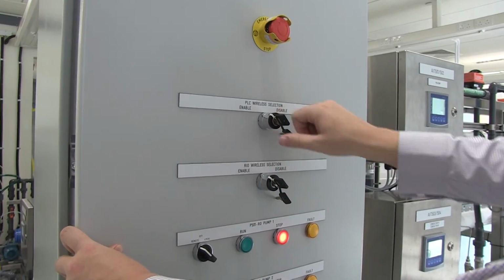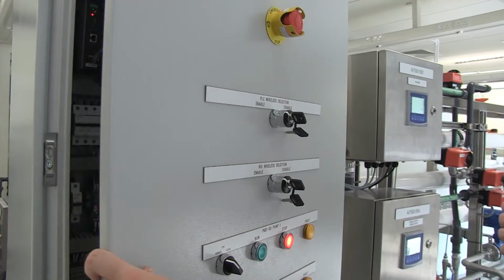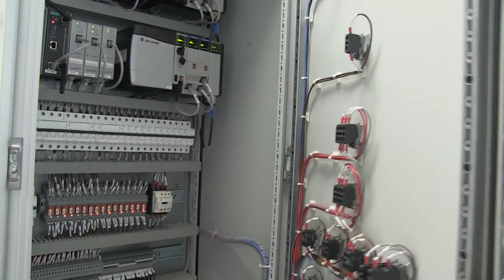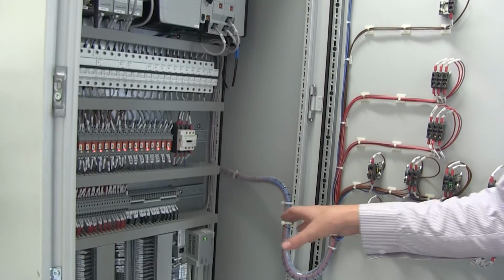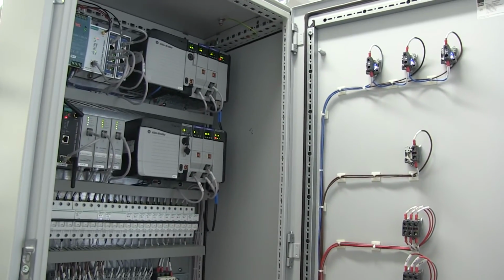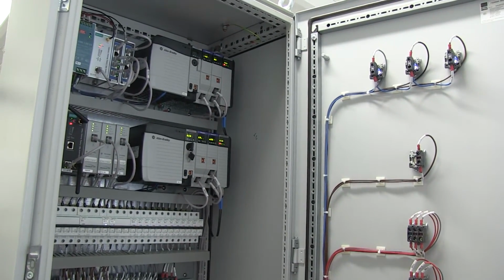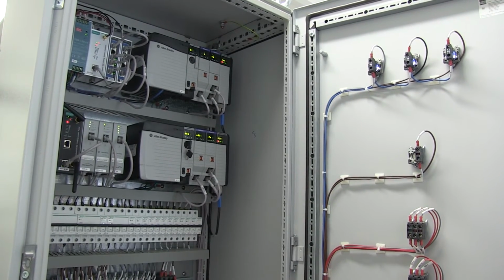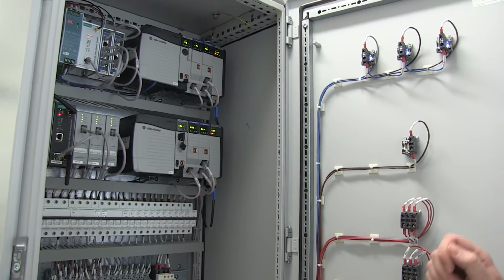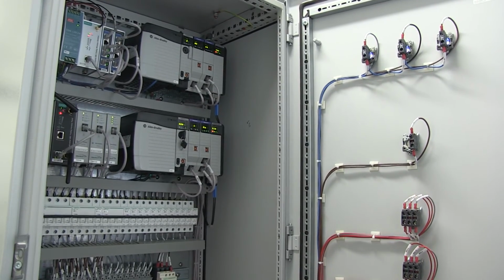If we enable the wireless communication here, we will automatically disable the wired connections, and in this case we would have switched both the level 0 network and the level 1 network of this PLC to wireless communication. So currently the PLCs are communicating with the remote I/O over a wireless link, and they're communicating with other PLCs over a wireless link as well.